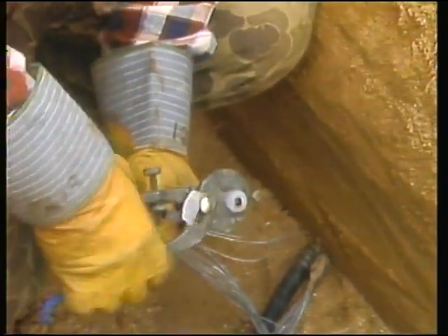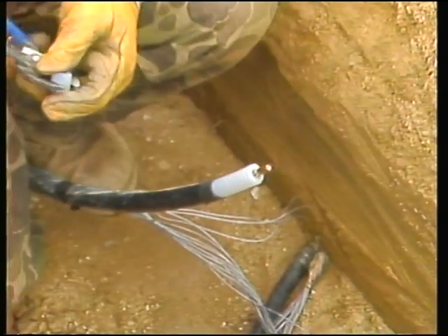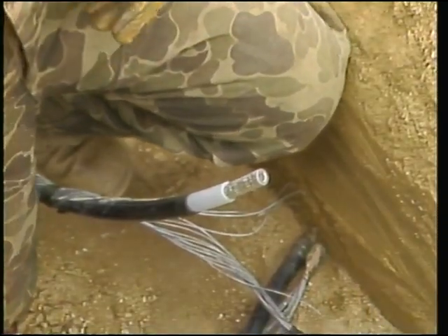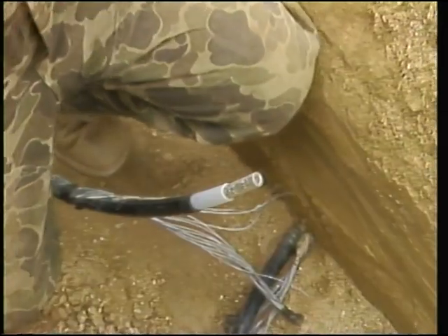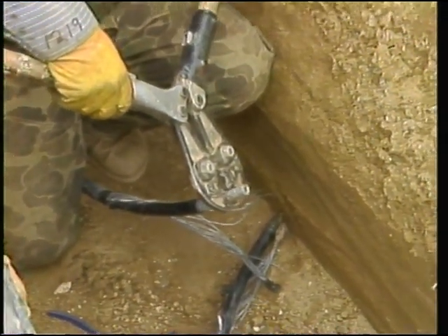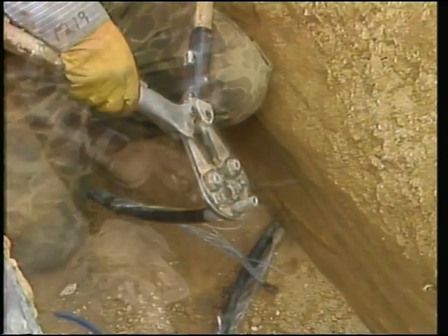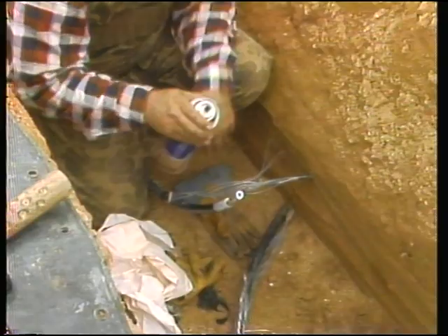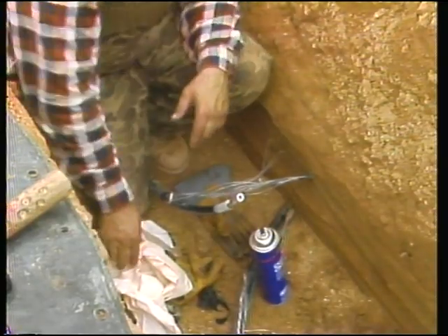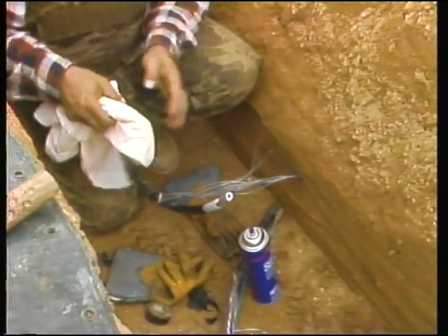Notice that the tool being used doesn't cut completely through to the conductor. Now the workman double checks that the tool and dies are correct for the job. After this, the compression connector can be installed and crimped into place on the first cable conductor. The insulation is then cleaned and wiped with an approved cleaning solvent or with the cleaning pads that may be supplied with the splice kit.